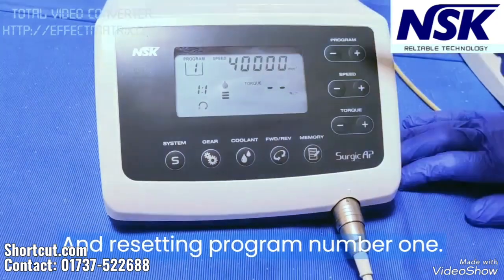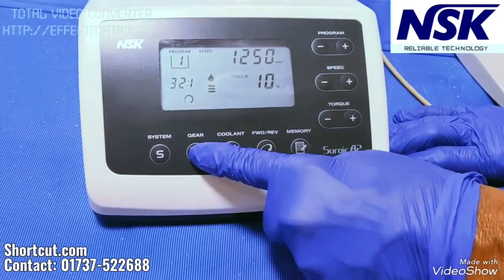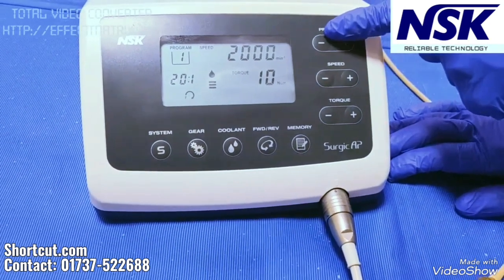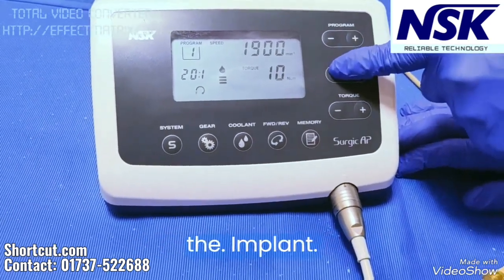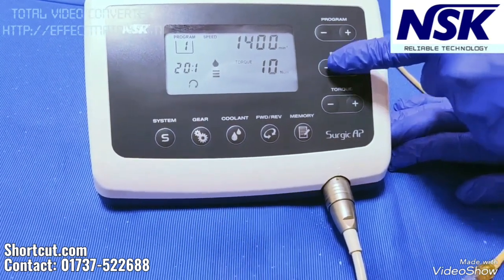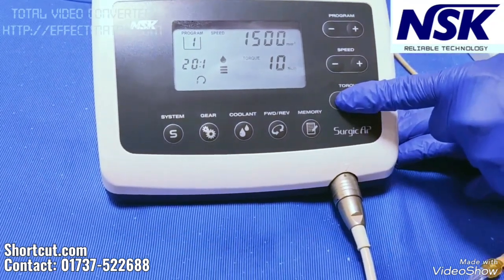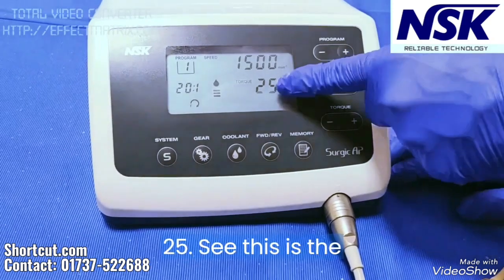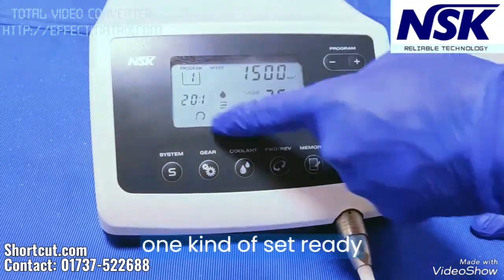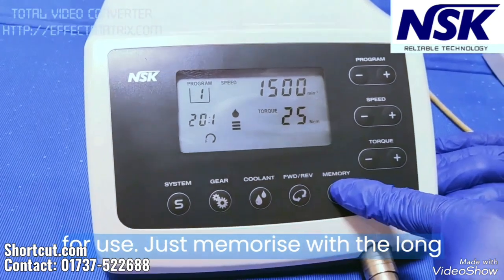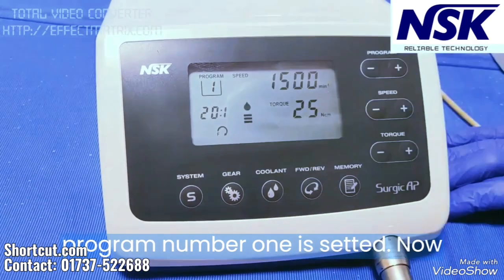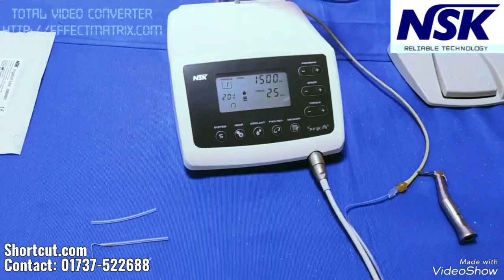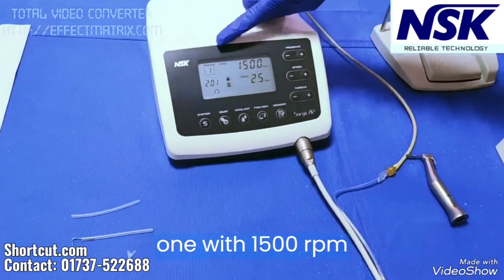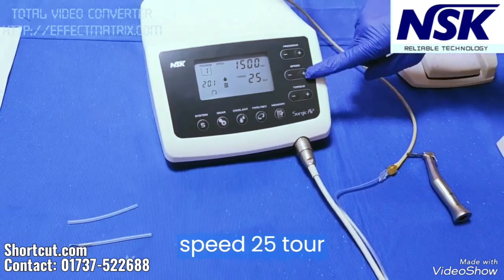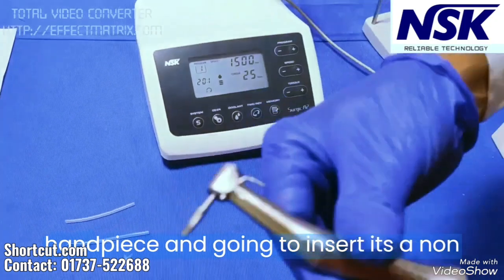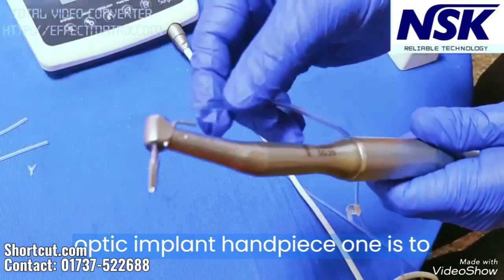I am setting program number 1 for the 20:1 handpiece, with speed according to the implant. For example, I am taking 1500 and torque 25. Now this is set, ready for use. Memorize it by long pressing the memory button. Now program number 1 is set and the unit is ready: 1500 rpm speed, 25 torque, with the 20:1 implant handpiece. I am going to insert it. It's a non-optic implant handpiece, 1:20.